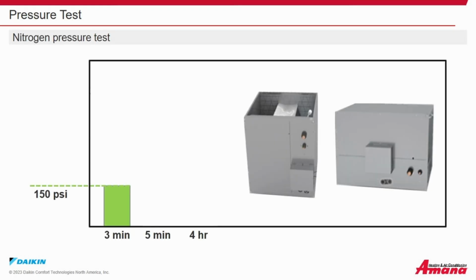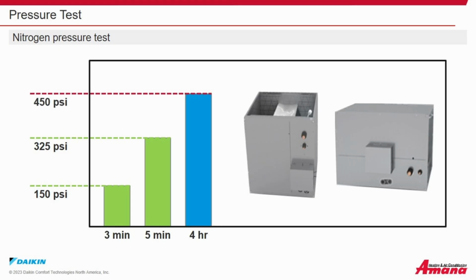Pressure test. Nitrogen pressure test. The first step of the pressure test should be 150 psi of nitrogen and hold that pressure for a total of 3 minutes. After 3 minutes, increase the nitrogen pressure to 325 psi and hold for 5 minutes. Next, increase the nitrogen pressure to 450 psi and allow that to stay in for a minimum of 4 hours to ensure that there are no leaks.